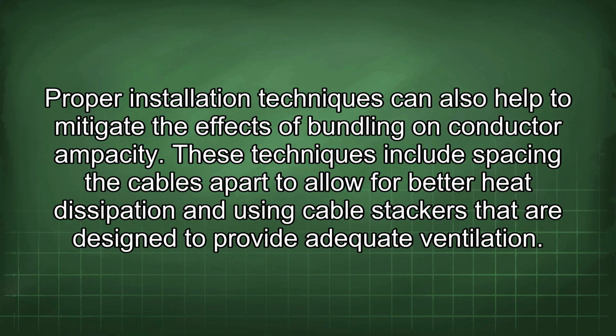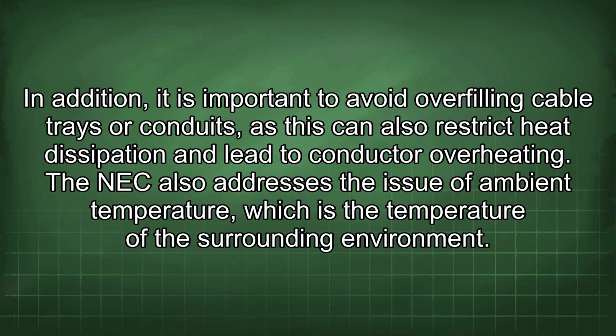Proper installation techniques can also help to mitigate the effects of bundling on conductor ampacity. These techniques include spacing the cables apart to allow for better heat dissipation and using cable stackers that are designed to provide adequate ventilation. In addition, it is important to avoid overfilling cable trays or conduits, as this can also restrict heat dissipation and lead to conductor overheating.